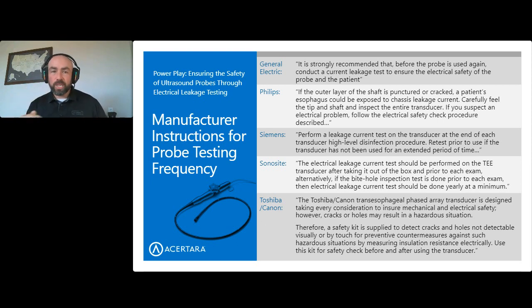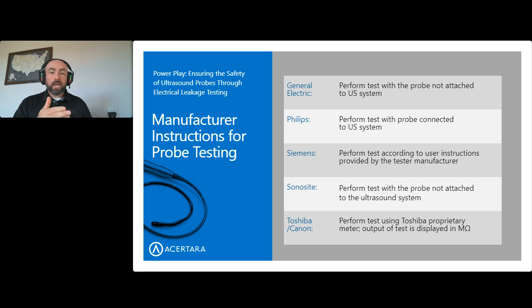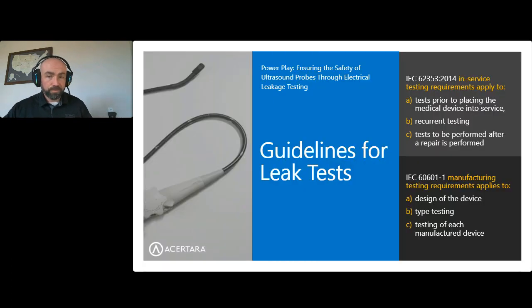But if you read through each of the manufacturers, they give instructions for how often you should test the probes and what you should be looking for when you're doing inspections, and ensuring that your team knows how to do these properly is available for whatever specific model of probe you have in your facility. Often this testing you also need to do while it's attached to the system, but what we're talking about is a test done independently of the system, and that is correlated to the measurements that you would do on the system, so that it's real world. It is a good example of what you would see if that probe was hooked up to the system and inside a patient. That's the real purpose of electrical leakage testing, to ensure that we're not going to hurt patients.